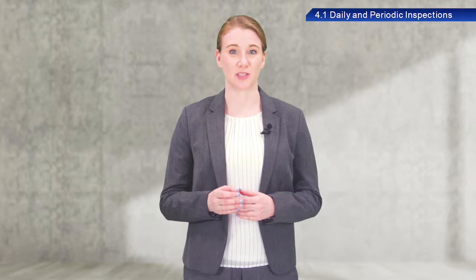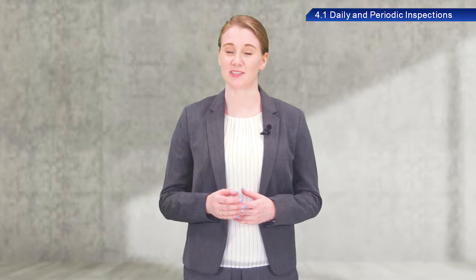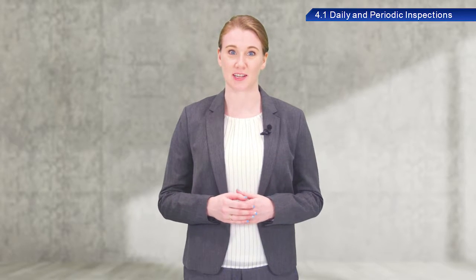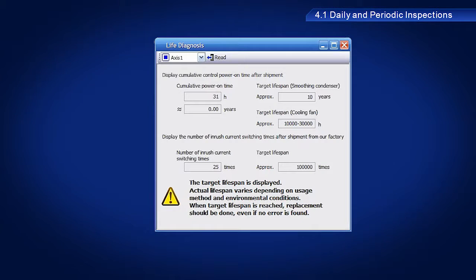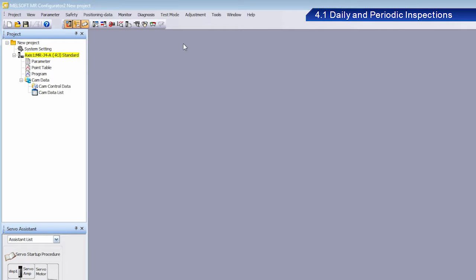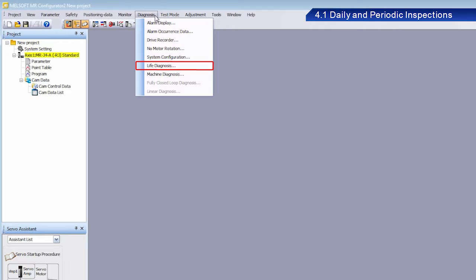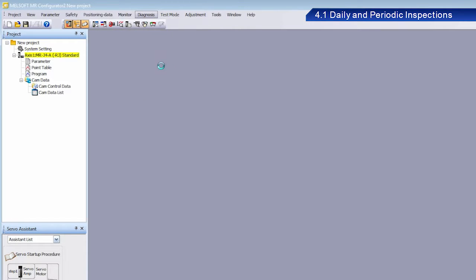MR Configurator 2 also includes a feature called Life Diagnosis function. This function lets you know when it is time to replace specific parts such as smoothing capacitors and relays. From the menu bar, select Diagnosis and then Life Diagnosis to view this status information.